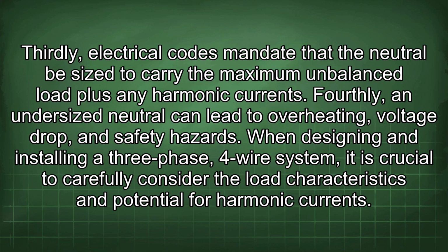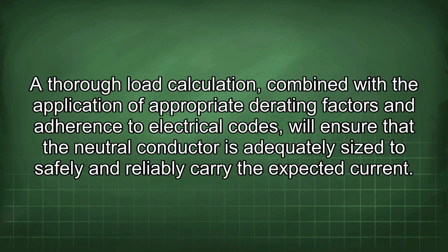Fourthly, an undersized neutral can lead to overheating, voltage drop, and safety hazards. When designing and installing a three-phase, four-wire system, it is crucial to carefully consider the load characteristics and potential for harmonic currents. A thorough load calculation, combined with the application of appropriate derating factors and adherence to electrical codes, will ensure that the neutral conductor is adequately sized to safely and reliably carry the expected current.